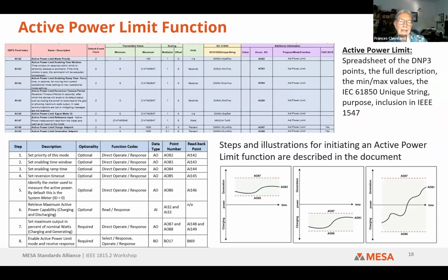What I'm showing here is the spreadsheet at the top, which shows the functions, the DNP3 points, the 61850 names, plus additional information. In the 1815.2 document, we've described step by step what you need to set for the function to be activated. Some steps may be optional if you've already set something — you don't have to reset everything all the time — but these are the steps you need to take at least initially.